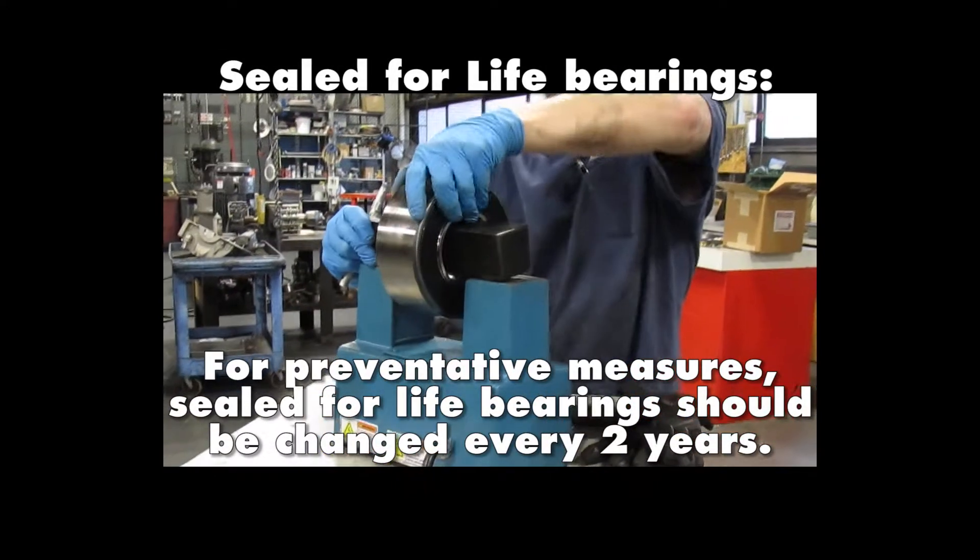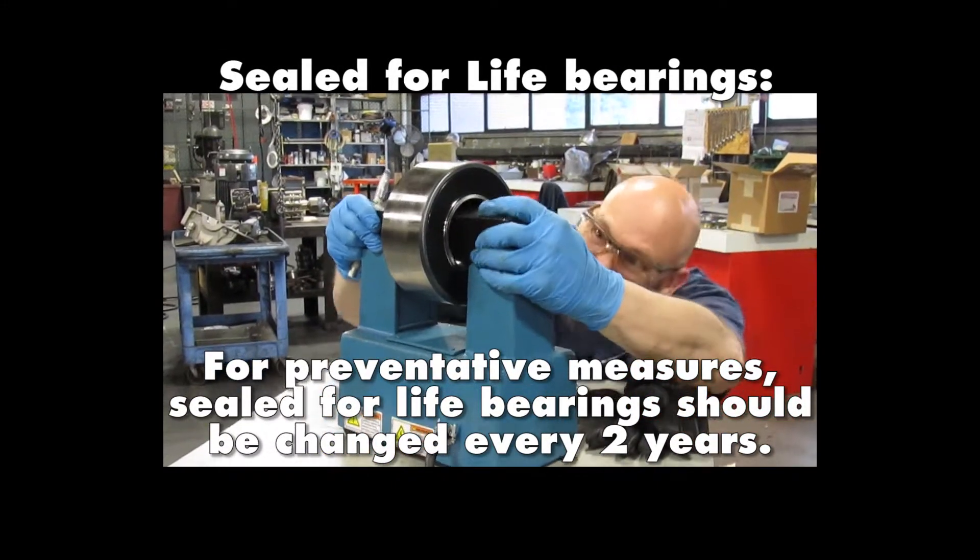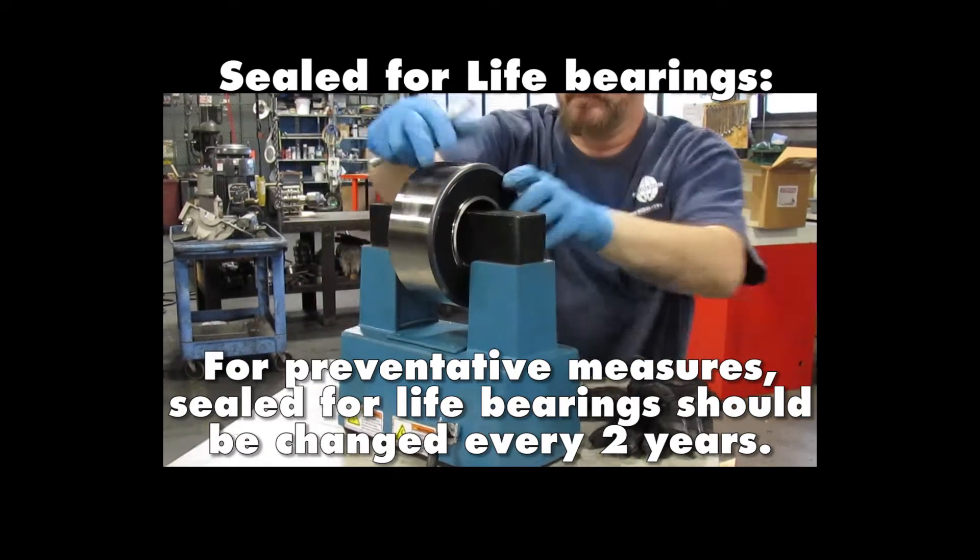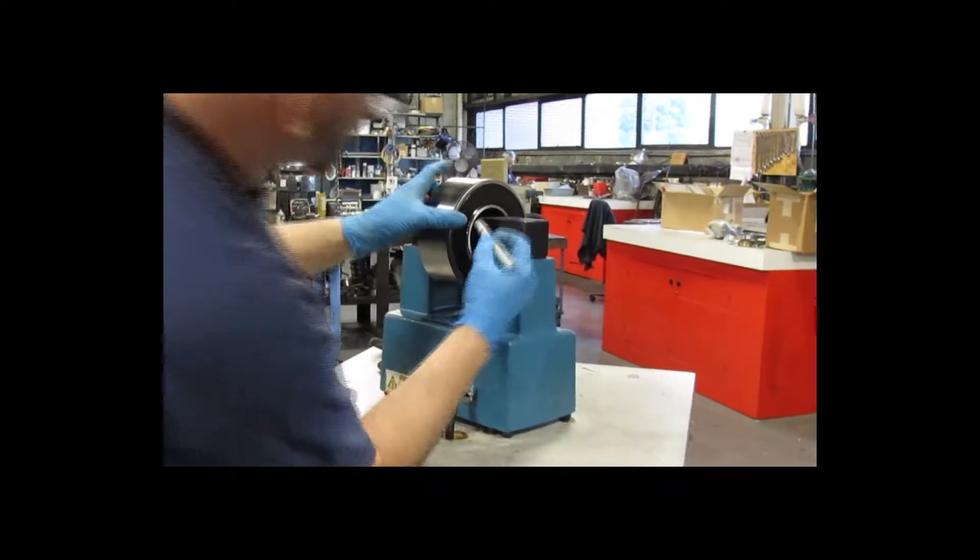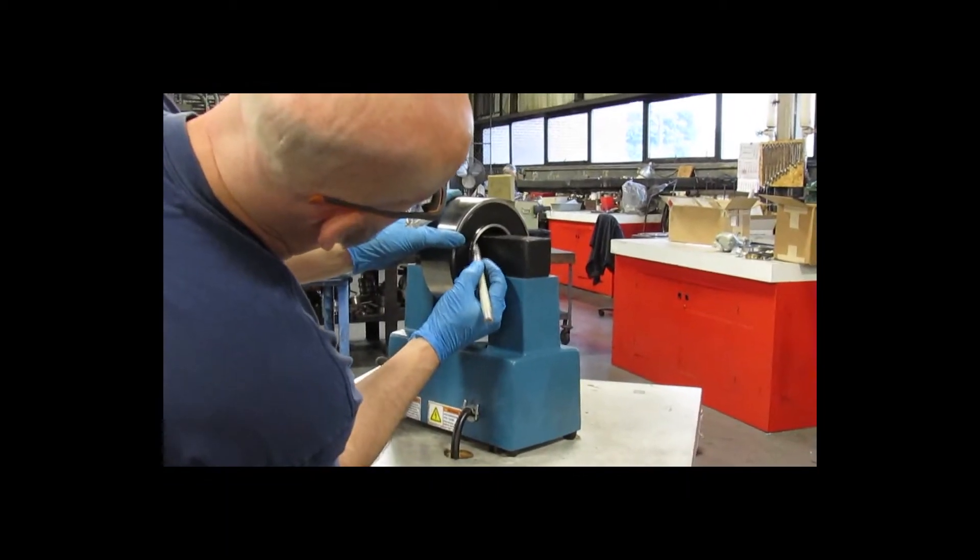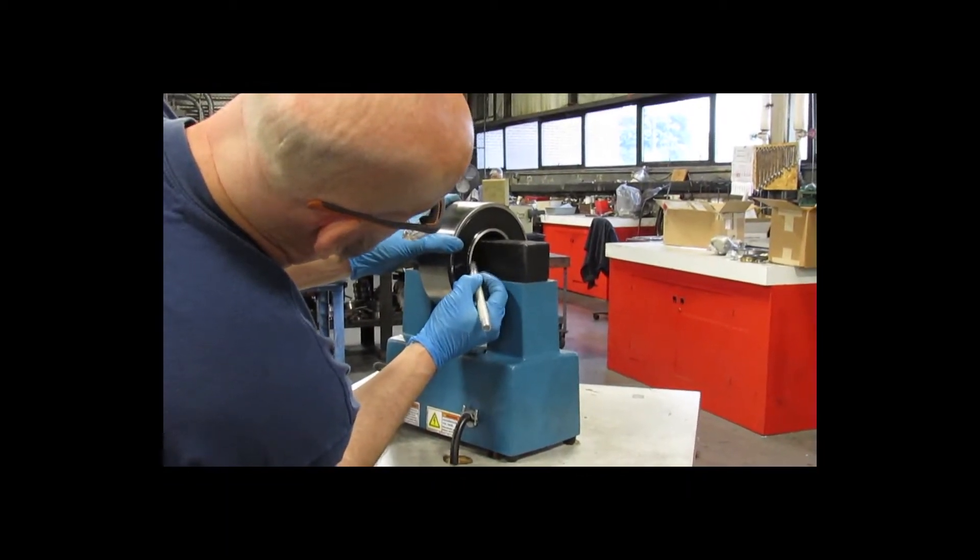This particular bearing is a sealed for life bearing. We don't want to heat this bearing up beyond 180 degrees Fahrenheit. I apply a small film on the inner race of the bearing with the bearing crayon, which will melt when the bearing reaches the proper temperature.